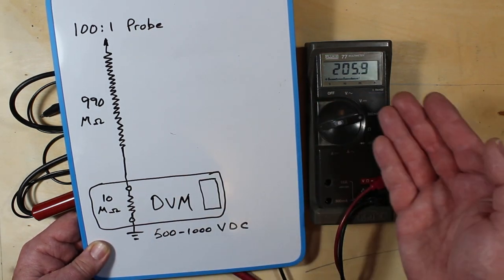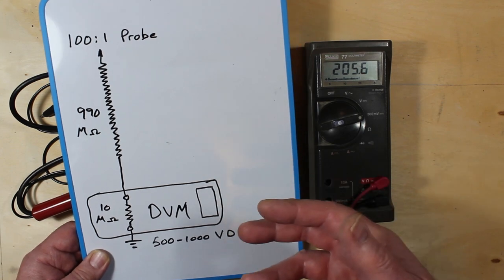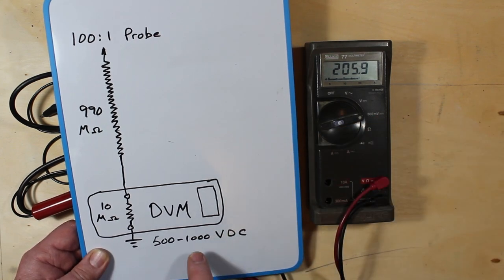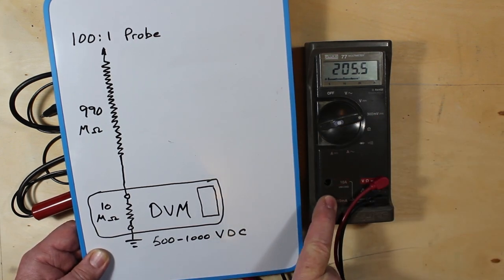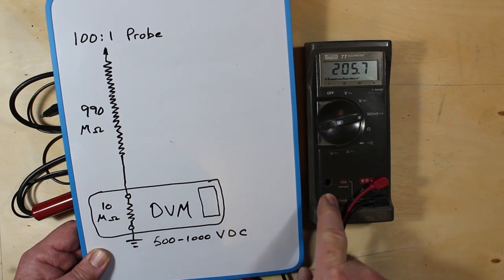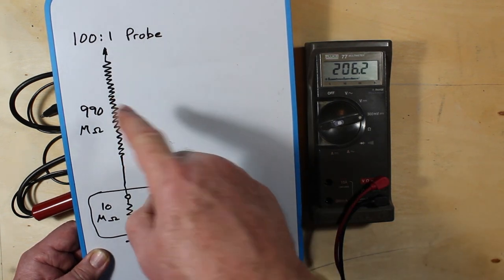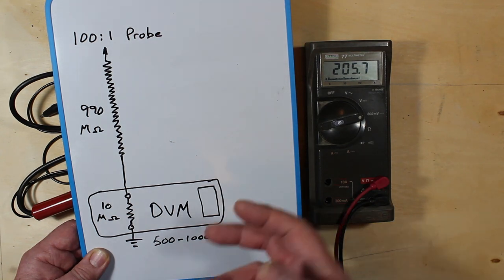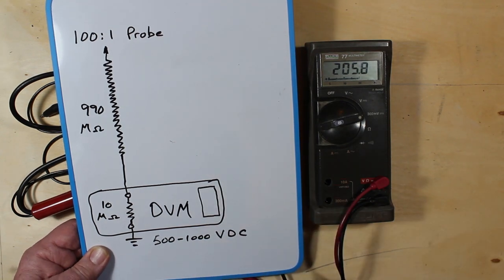And obviously be very careful if you're going to be measuring any of these sorts of voltages. Now this meter is made so that it can handle 1,000 volts. So 1,000 times 100 does not mean that you can safely measure 100,000 volts.